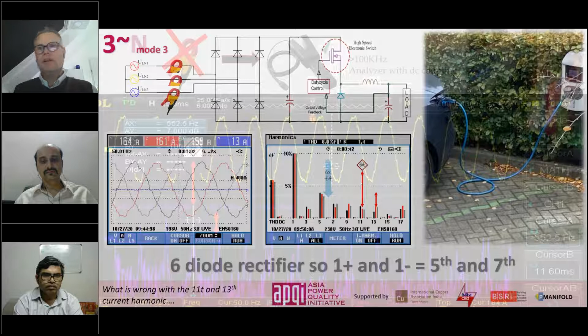Shunts are the best there are, and then you can measure it very well, but I cannot measure high frequency with a low frequency current clamp. So I used this current clamp, connected it to my oscilloscope, and checked the phases and the neutral.